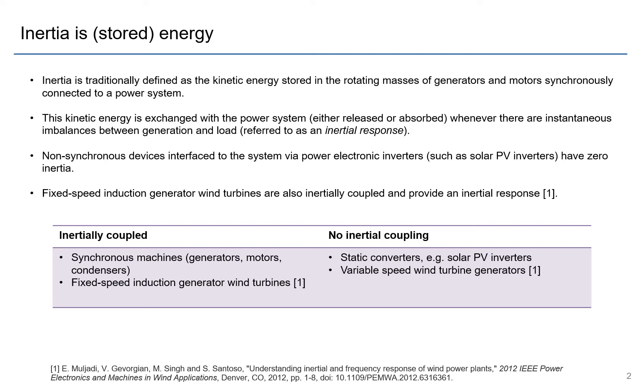Non-synchronous devices that are connected to the system via power electronic inverters, such as solar PV or type 4 wind turbines, they have zero inertia—there's no inertial coupling there. And it's been shown also that fixed-speed induction generator wind turbines are actually inertially coupled and do provide an inertial response, as per this reference one here.